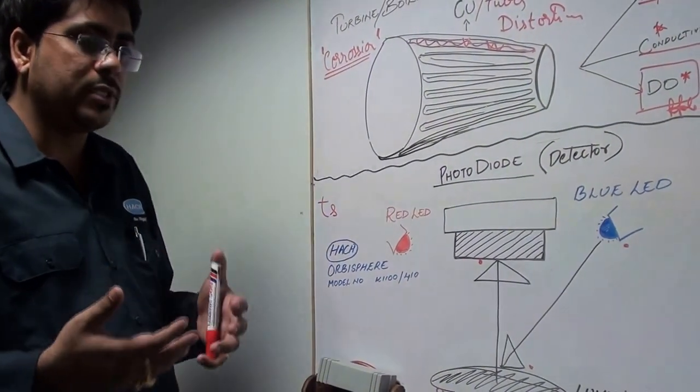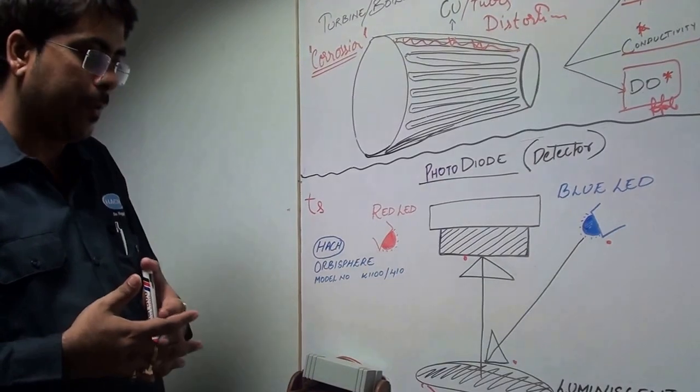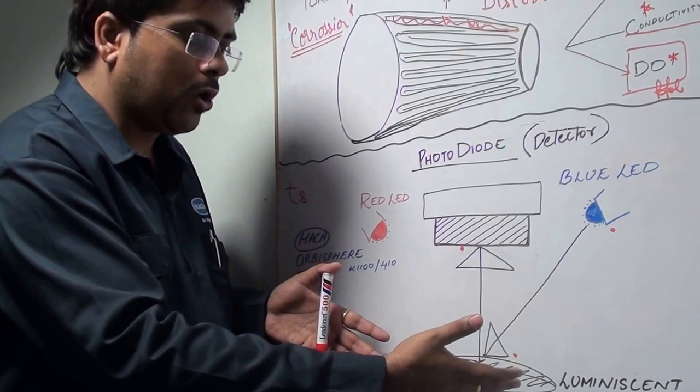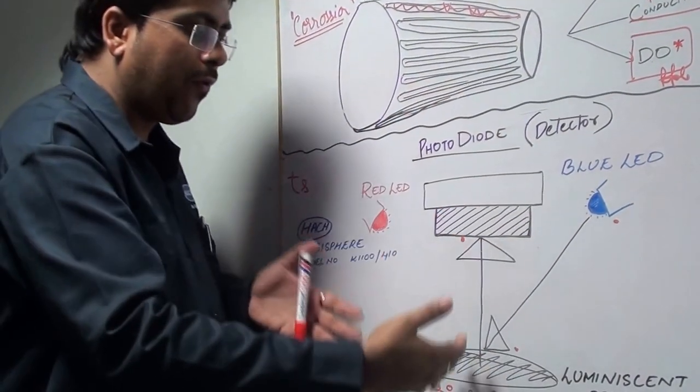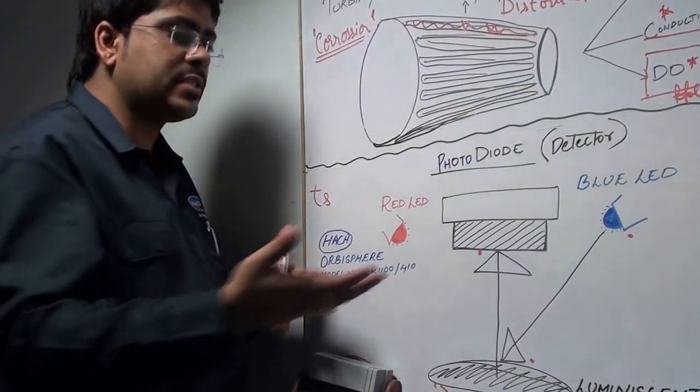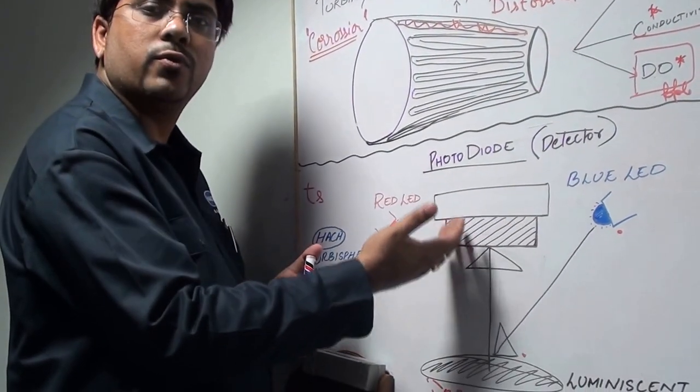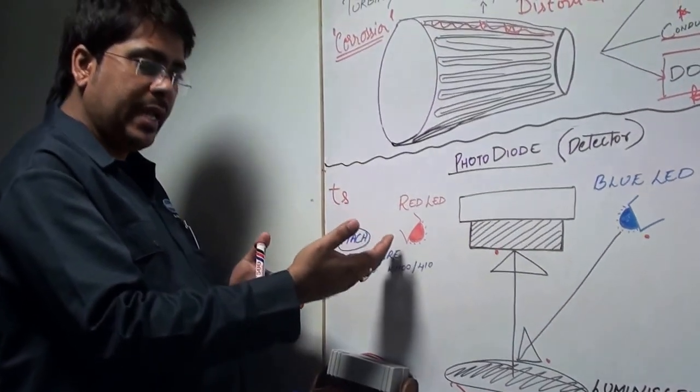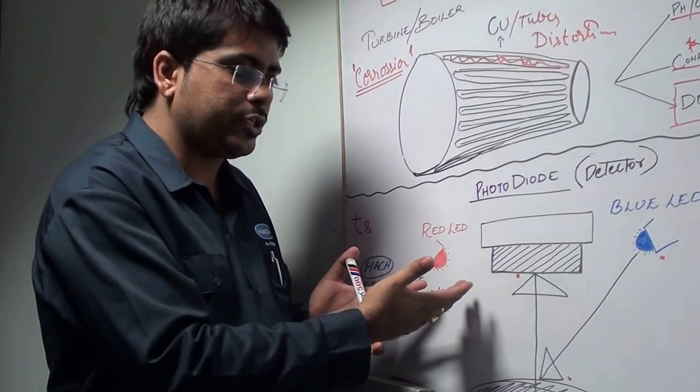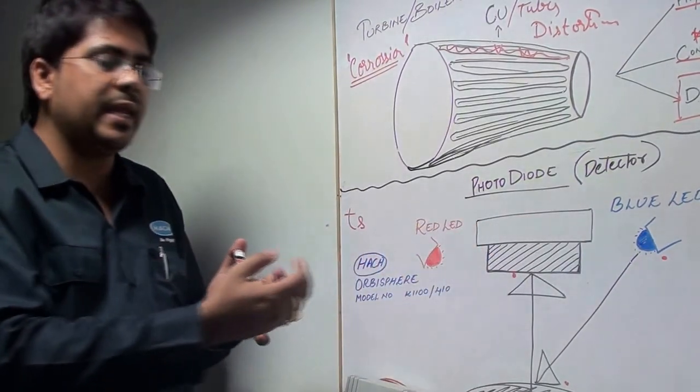The most important component is a black spot which is basically a luminescence spot. This works through the principle of luminescence. When blue LED light falls on the luminescence spot, it gets excited, emits radiation, and the radiation gets detected in the photodiode. The red LED consecutively does the referencing action.